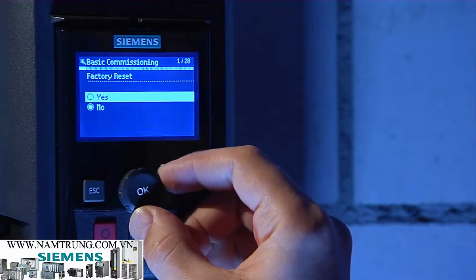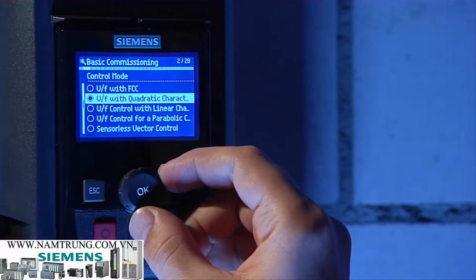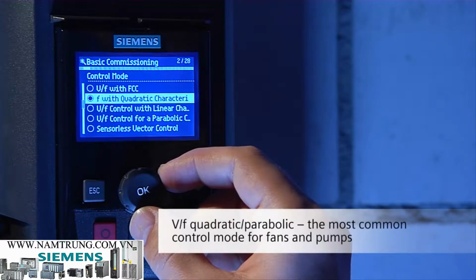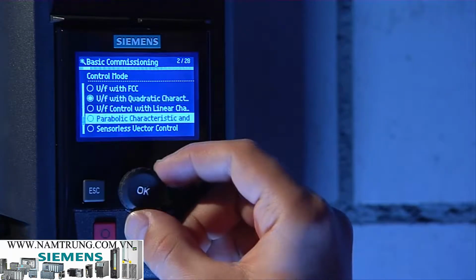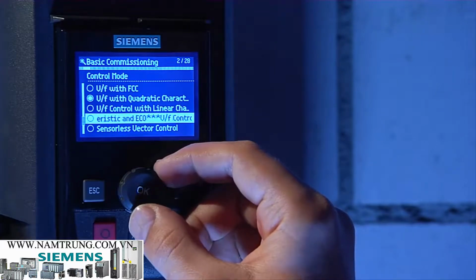In the next step, select the control mode. V/f with parabolic characteristic, the most common HVAC control method, is already pre-selected. Use V/f parabolic with eco mode for saving even more energy. In this mode, G120P will reduce the output voltage as much as possible without reducing the speed of the motor.